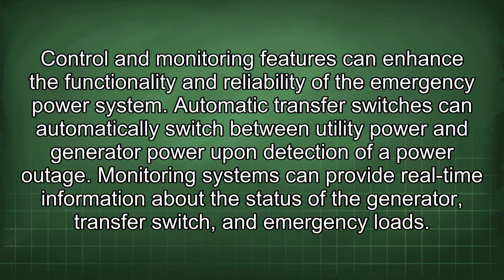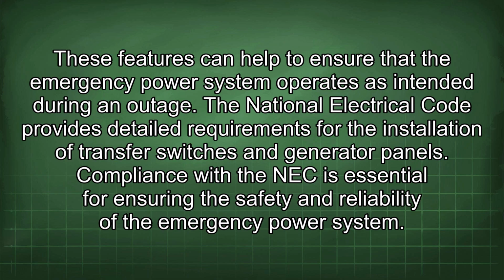Control and monitoring features can enhance the functionality and reliability of the emergency power system. Automatic transfer switches can automatically switch between utility power and generator power upon detection of a power outage. Monitoring systems can provide real-time information about the status of the generator, transfer switch, and emergency loads. These features can help to ensure that the emergency power system operates as intended during an outage.